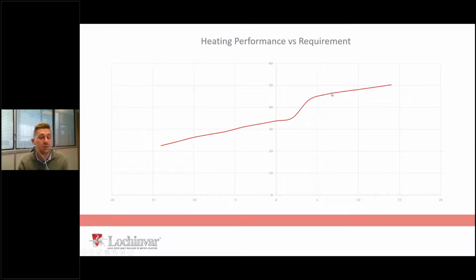The European standard for measuring the performance of an electric heat pump on any manufacturer's data sheet will be the EN reference, and it will be plus 7 degrees centigrade, and there'll be 2 flow temperatures given generally, but usually 35 degrees. So this 45 kilowatt heat pump is 45 kilowatts when the outside air temperature is 7, but in real life, if you were to receive a quotation from us for one, on paper it would look over-spec, because the kilowatt rating of that heat pump is only going to be the value at your design outside air temperature. So for me, I work with a lot of people in the City of London. If I'm working in the City of London, typically your outside design temperature is going to be like -2.